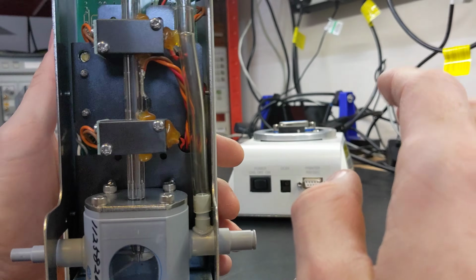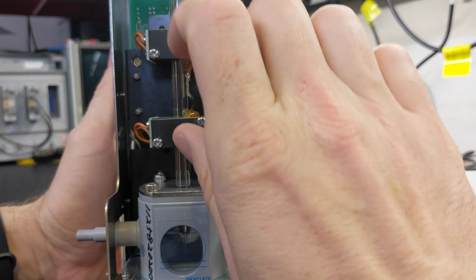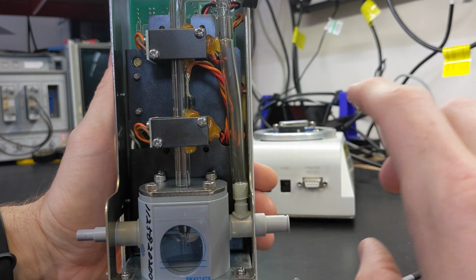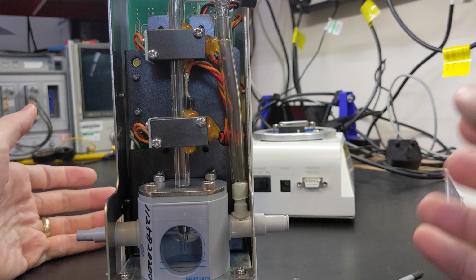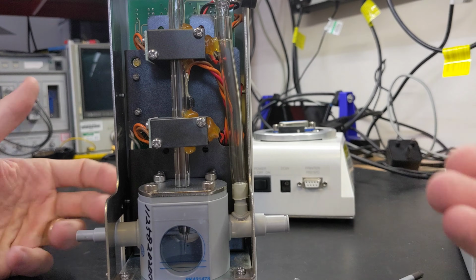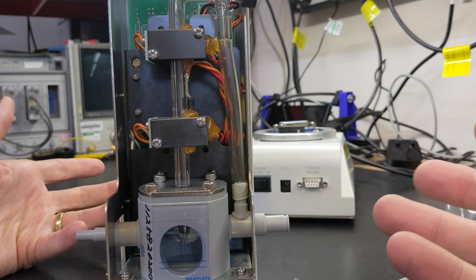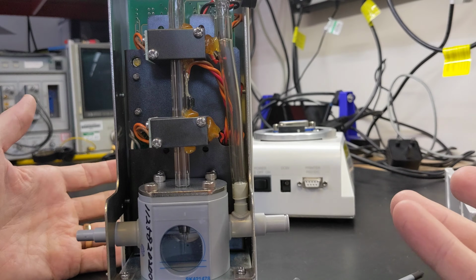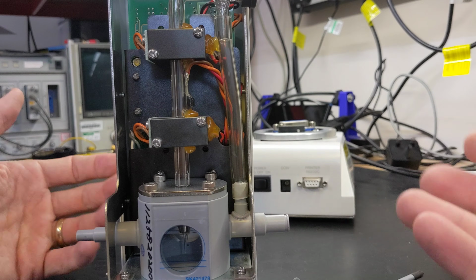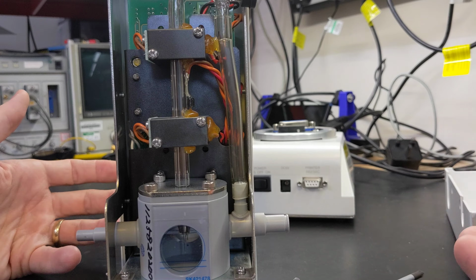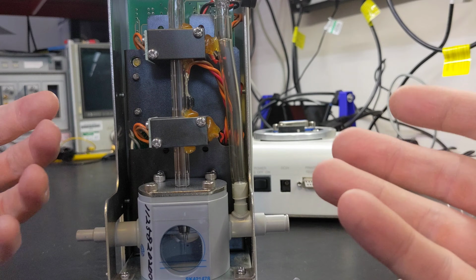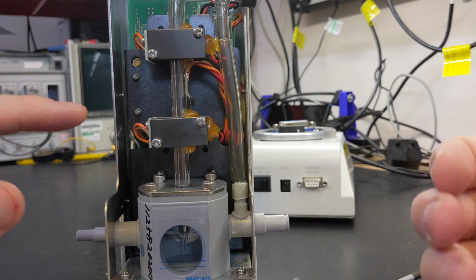From first principles, this is really nice - you directly measure a volume of gas displaced. Now the problem is a volume of gas isn't the same as a mass of gas - you need temperature and pressure to correct for the density of the gas. They obviously need that in here as well, since we want to get to mass flow, which is key for our mass flow controllers. But here we have a very precise measurement of volume.